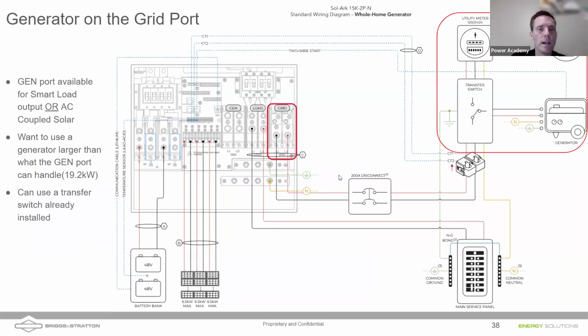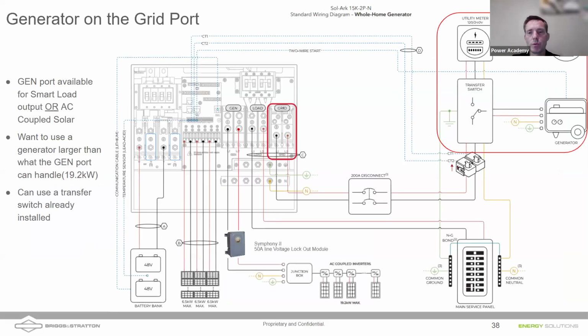Okay, so I'd like to show you, can we do a generator when we've got AC coupled solar? And the answer is yes, especially if you've got a Briggs and Stratton transfer switch. What we can do to prevent the AC coupled solar from backfeeding the generator during a low battery grid down event, where the solar has started up the generator and then solar is present, is we can put a lockout module on there. So it is important, the AC coupled solar might see that generator signal as grid presence in a grid down event. And we don't want to backfeed that AC coupled solar into the generator, because we could potentially burn out the controller, right?